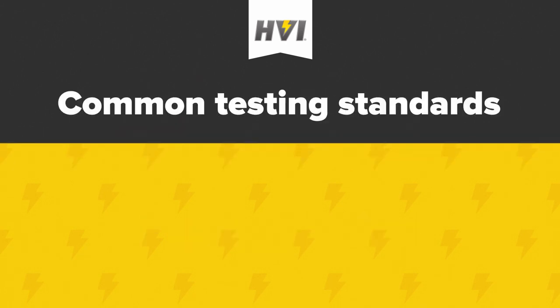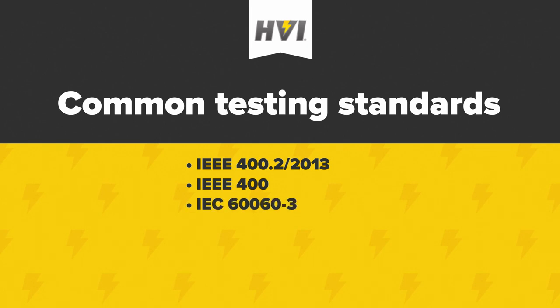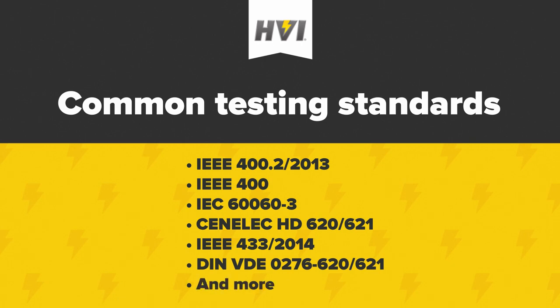HVI's VLF E-Series are advanced VLF, or very low frequency, AC HIPOTs used for the testing of high voltage cables and motors or generators. Common testing standards that the VLF E-Series support include IEEE 400.2 2013, IEEE 400, IEC 60060-3, CENELEC HD 620/621, IEEE 433-2014 for motors or generators, and many other local standards.